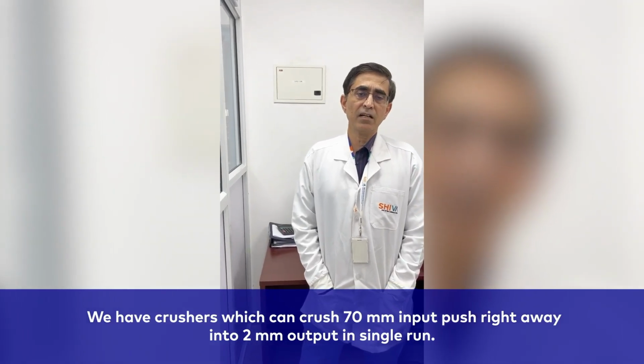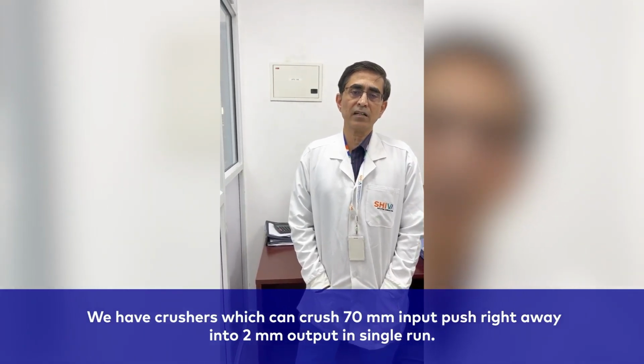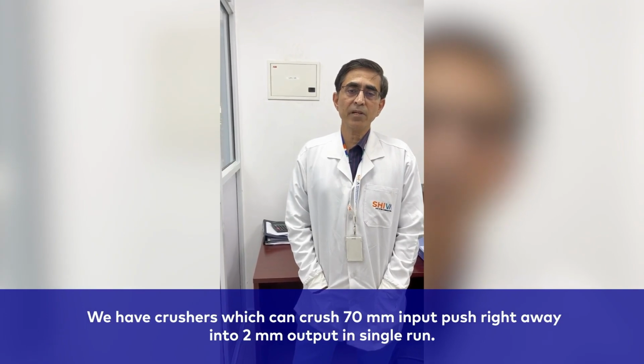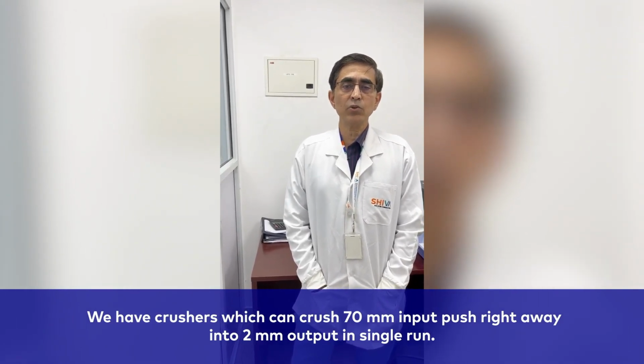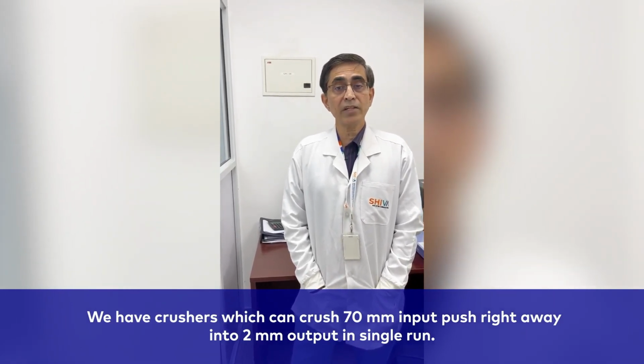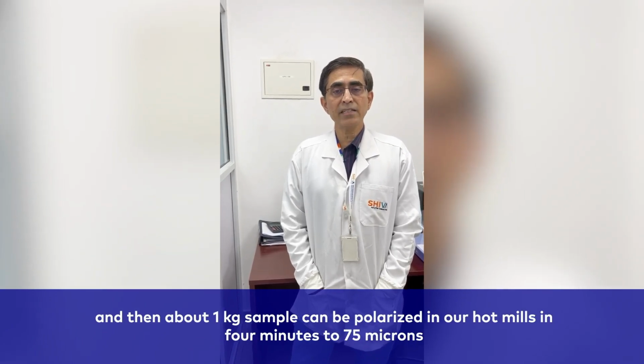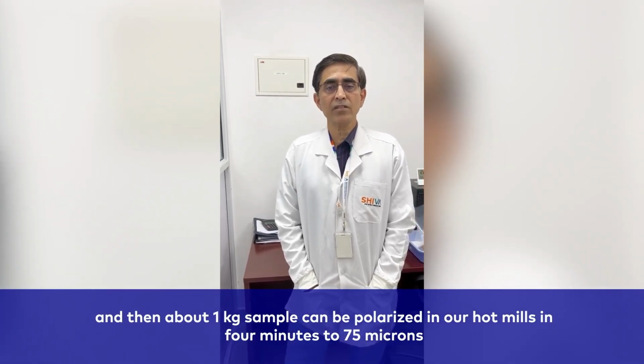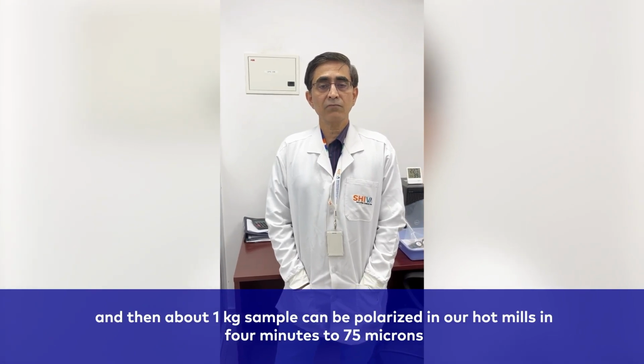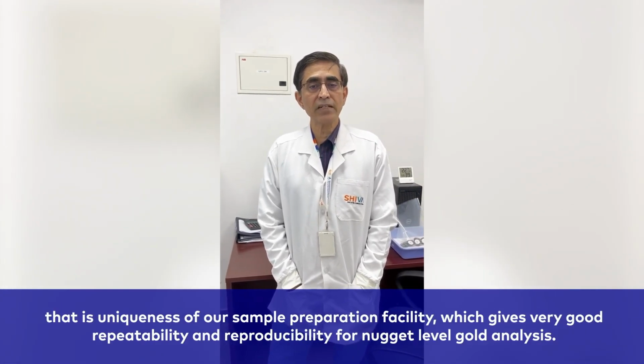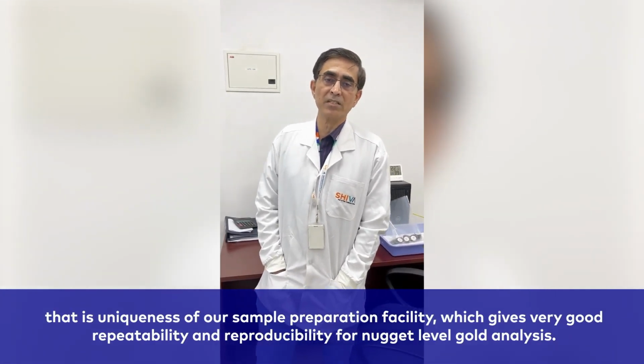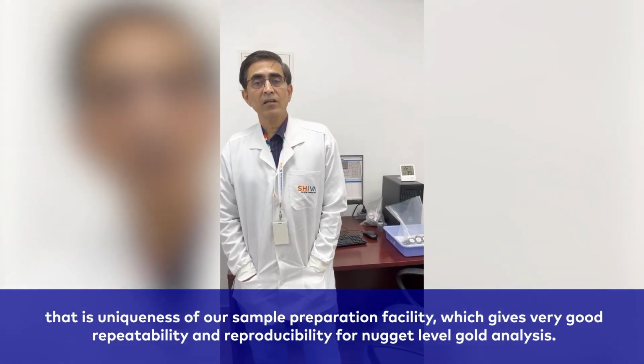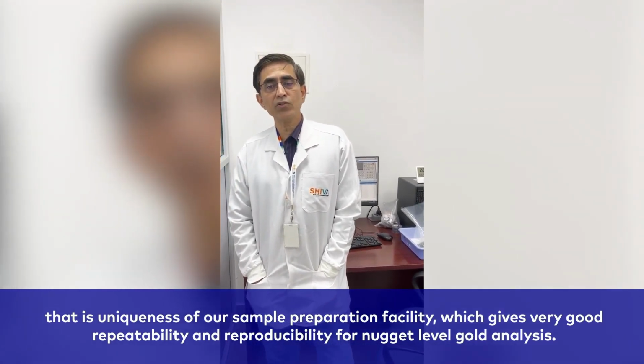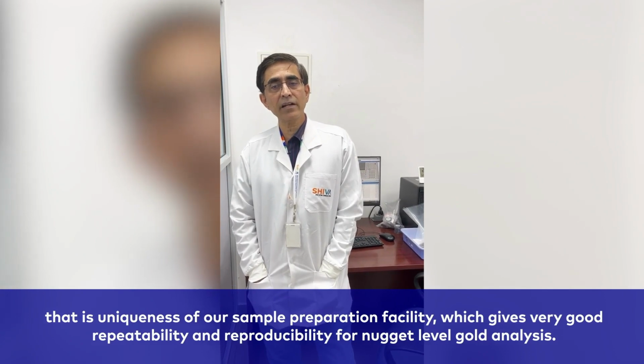We have crushers which can crush 70 mm input straight into 2 mm output in a single run, and then about 1 kg of sample can be pulverized in our pot mills in 4 minutes to 75 microns. That is the uniqueness of our sample preparation facility, which gives very good repeatability and reproducibility for nugget level gold analysis.